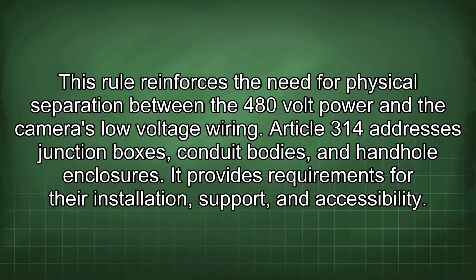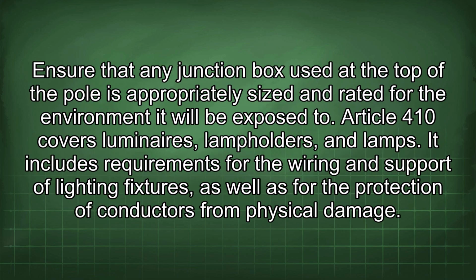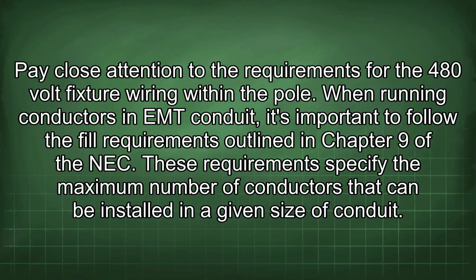Article 314 addresses junction boxes, conduit bodies, and handhole enclosures. It provides requirements for their installation, support, and accessibility. Ensure that any junction box used at the top of the pole is appropriately sized and rated for the environment it will be exposed to. Article 410 covers luminaires, lamp holders, and lamps. It includes requirements for the wiring and support of lighting fixtures, as well as for the protection of conductors from physical damage. Pay close attention to the requirements for the 480-volt fixture wiring within the pole.